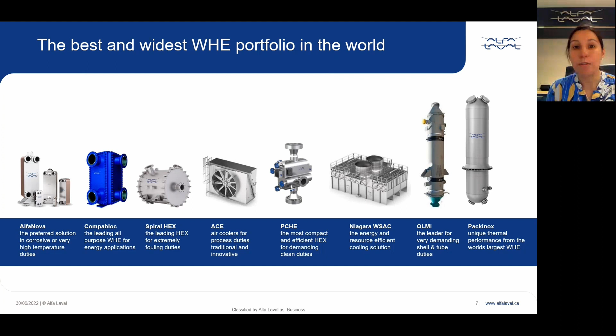Now, the Compabloc is a welded plate heat exchanger. It has similarities with the gasketed plate exchanger, which I'm sure you are already familiar with. And it's based on the same concept of corrugated plates that provide a very high efficiency because of a highly turbulent flow, which also promotes higher heat transfer coefficients within the design. Now, there are differences between the gasketed design and the Compabloc design. The main one being that the gaskets between plates have been totally eliminated. The Compabloc plates are bound together by welding. So there are no gaskets in contact with the fluids. So that helps provide a wider range of applications in terms of chemical compatibility, temperature, and pressure.